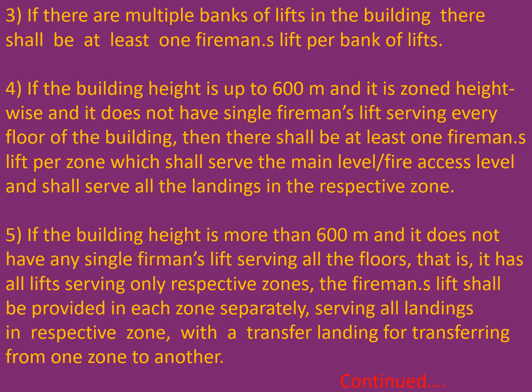We are talking of a very high skyscraper type of building in which each group of 30 floors is provided a service equipment area. Fifth, if the building height is more than 600 meter and it does not have any single fireman lift serving all the floors, that is, it has all lifts serving only respective zones, the fireman's lift shall be provided in each zone separately, serving all landings in respective zones with a transfer landing for transferring from one zone to another. This is to be continued further.